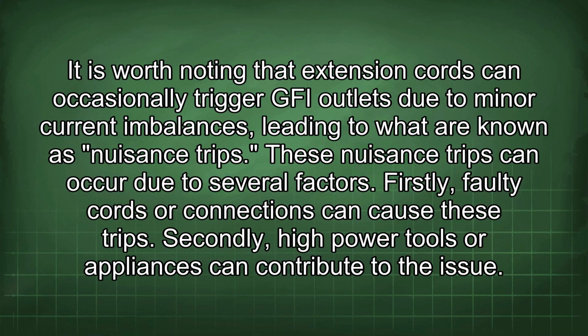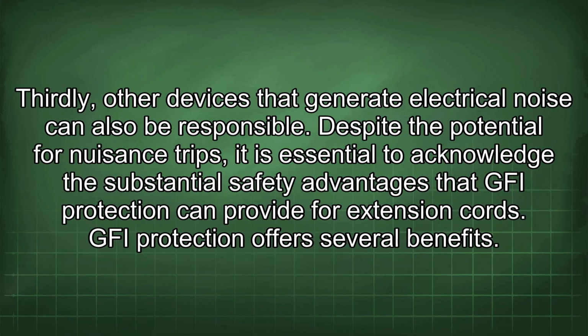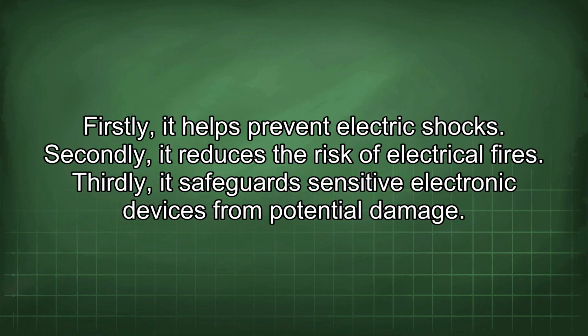These nuisance trips can occur due to several factors. Firstly, faulty cords or connections can cause these trips. Secondly, high-power tools or appliances can contribute to the issue. Thirdly, other devices that generate electrical noise can also be responsible. Despite the potential for nuisance trips, it is essential to acknowledge the substantial safety advantages that GFI protection can provide for extension cords. GFI protection offers several benefits. Firstly, it helps prevent electric shocks. Secondly, it reduces the risk of electrical fires. Thirdly, it safeguards sensitive electronic devices from potential damage.